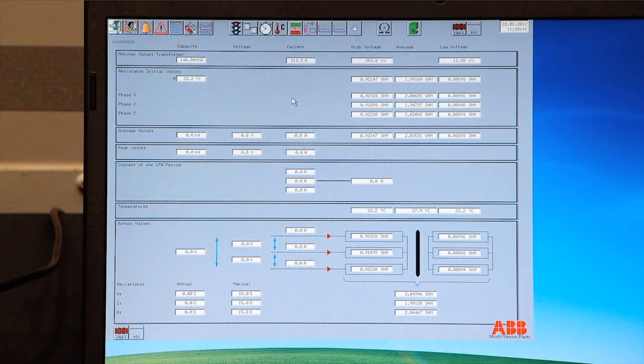When the measuring button turns green, the following actions are carried out by the control system. The proper voltage is calculated and set. The converter gets the command for the average voltage reference measurement. The average resistance is measured in the converter and is stored in the PLC together with the reference temperature for the measurement. If the HV measurement has been selected, the PLC will send a command to the converter to measure the resistance in the high voltage winding.